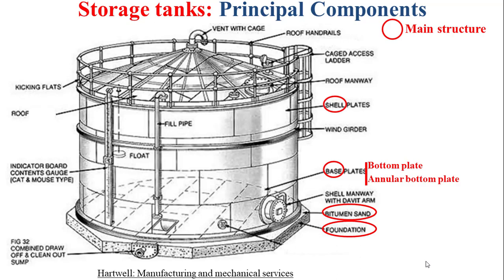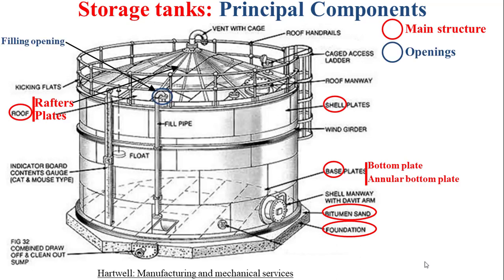We have the shell composed of welded shell plates, and we have the roof composed of rafters that hold the roof cladding, which is composed of welded roof plates. The storage tank is also composed of openings: we have the filling opening via the fill pipe, and the draw-off opening that can also be used for the clean-out of the storage tank. We have the manways that can be located in the shell and in the roof, and we have the vent opening.